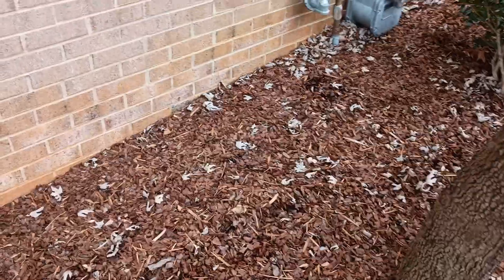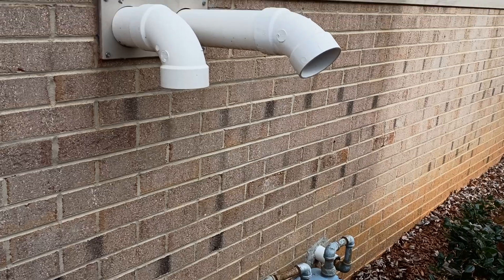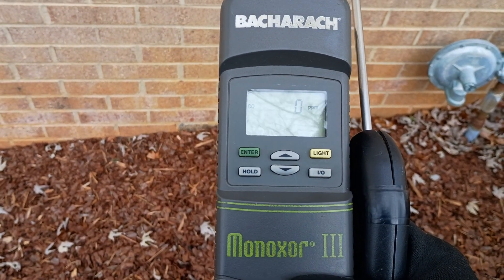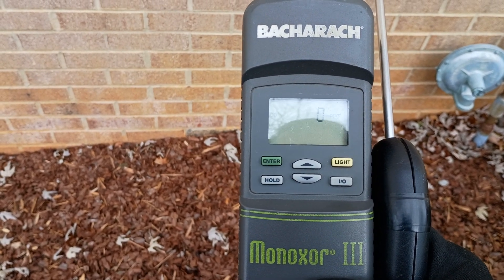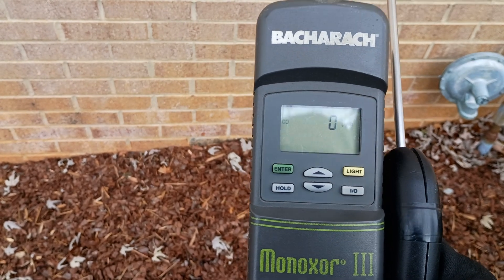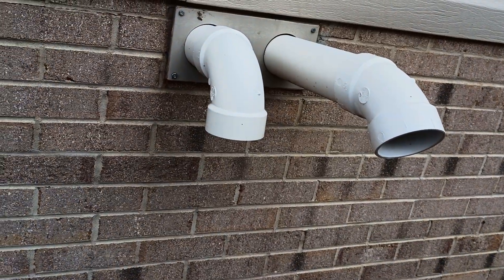Over the years, my preferred method of diagnosing a bad heat exchanger is to come out here to the vent pipes and sample the CO. Unfortunately, Bacharach doesn't make the good old Monoxor II or Monoxor III anymore, and basically all you can get are the big fancy detectors that measure everything — they're a thousand dollars and you don't need all that. This is one of my favorite tools here. It's got some age on it, but you keep up with the sensors and send it in to Bacharach every now and then.